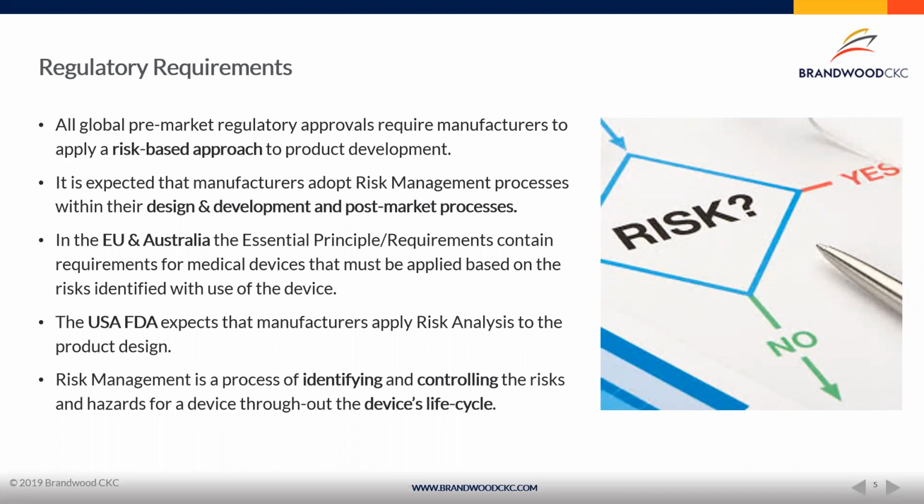It's expected that manufacturers adopt risk management processes within their design and development and post-market process. Key here is both sides. So not only when you're designing and developing this, but also how are you taking inputs from when the actual device is in the field and bringing that back to your design and development to do continuous improvements, or to address things that may not have been identified as a risk previously, but now you've taken that in, you're processing it, and you're going through the right steps to show whether there's mitigation or any kind of controls in place for those risks.